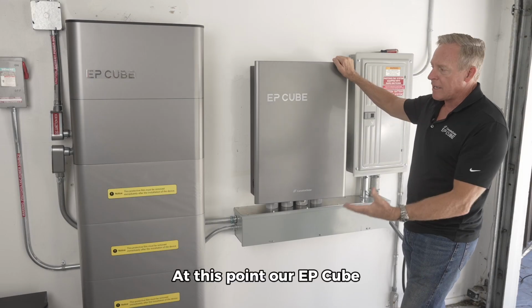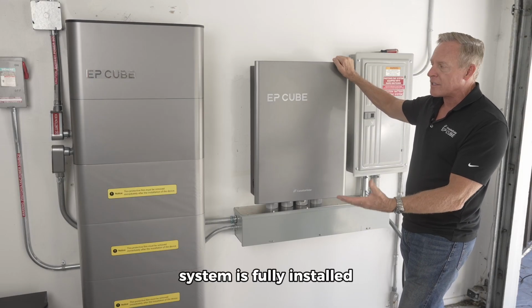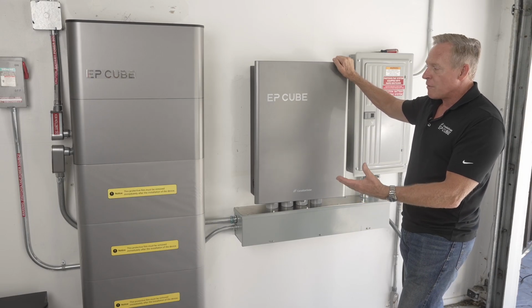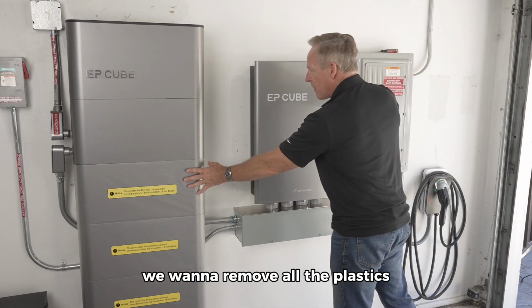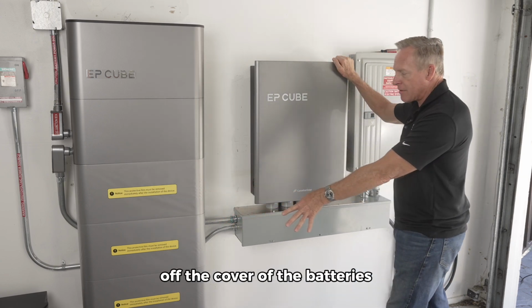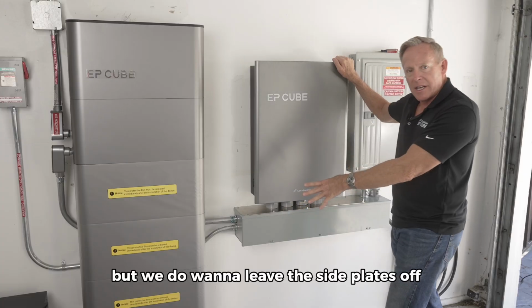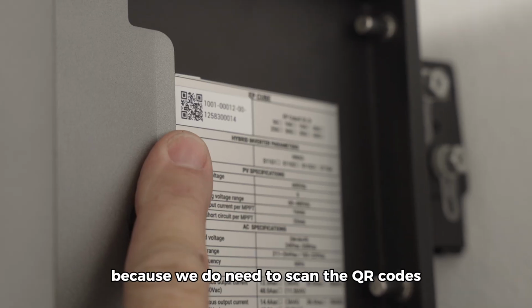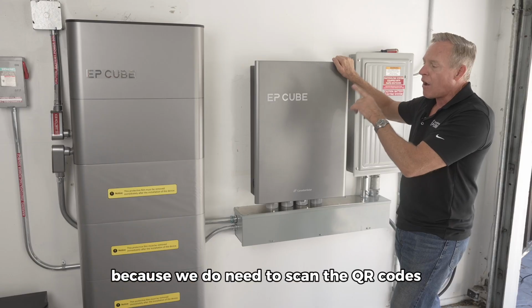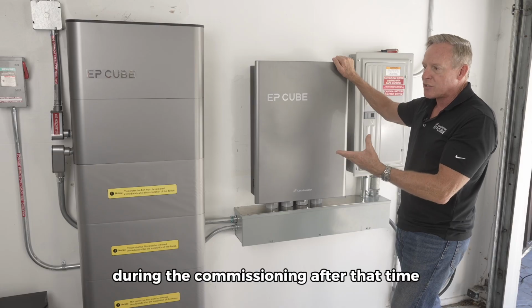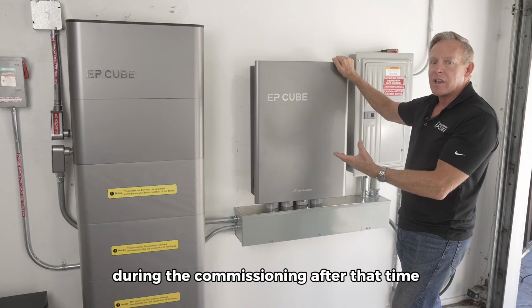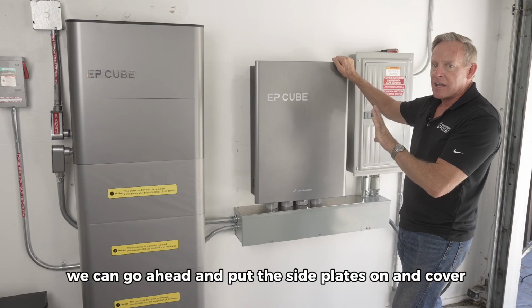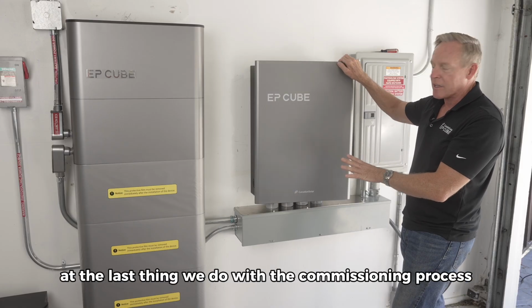At this point, our EP Cube system is fully installed and it's ready for commissioning. One thing we want to do is remove all the plastics off the cover of the batteries, but we do want to leave the side plates off during commissioning because we do need to scan the QR codes on all of the individual batteries during the commissioning. After that time, we can go ahead and put the side plates on and cover, the last thing we do with the commissioning process.